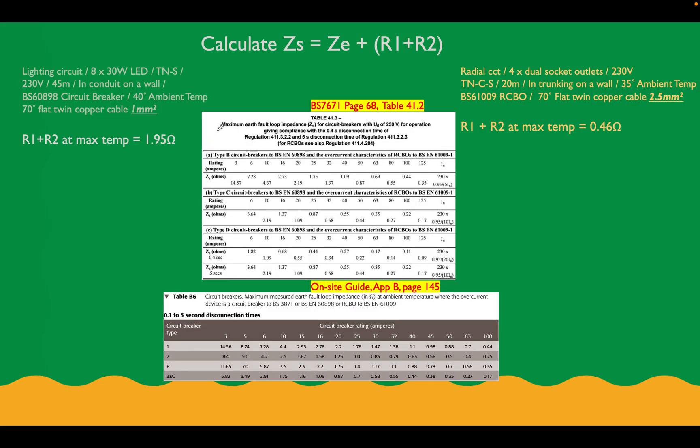Okay, so look at the top of our formula we can see. We know this already. ZS is equal to ZE, which is the external resistance, plus the R1, R2 value, which we've calculated here. So our earth fault loop impedance value is going to be equal to our ZE, so the earth fault loop impedance for the external part of the circuit, plus the part of our circuit which we've installed.